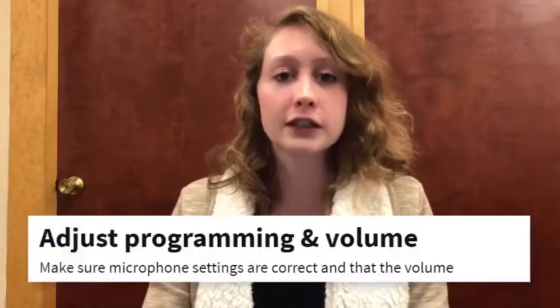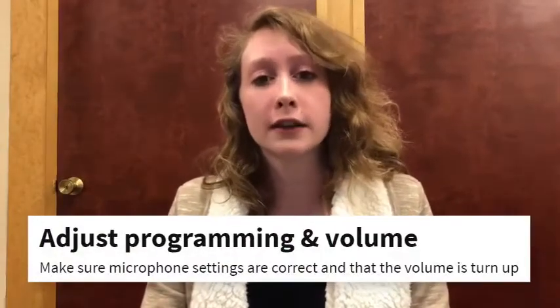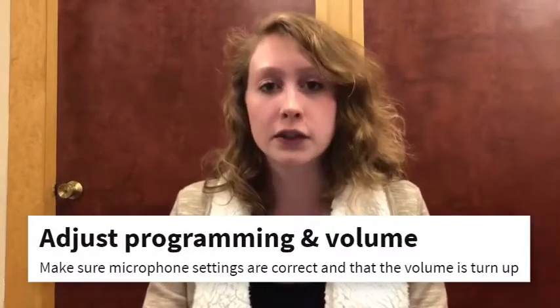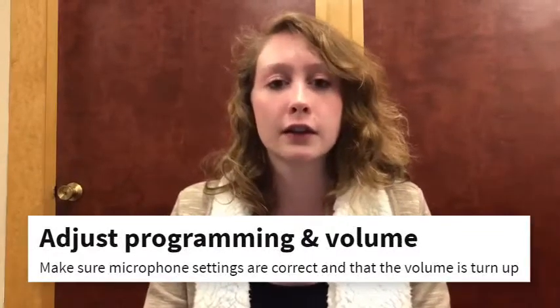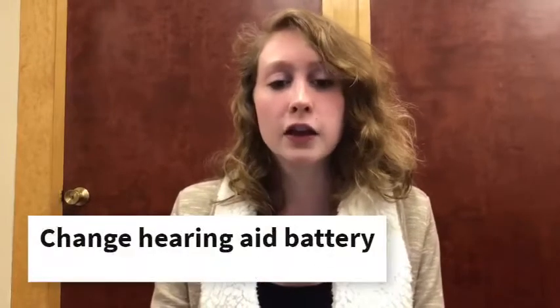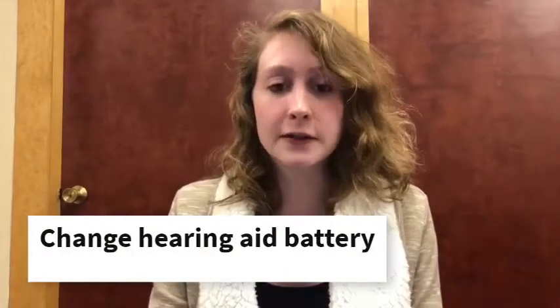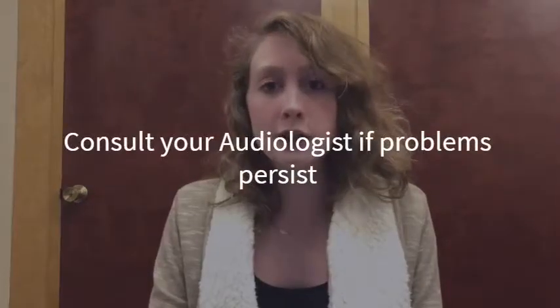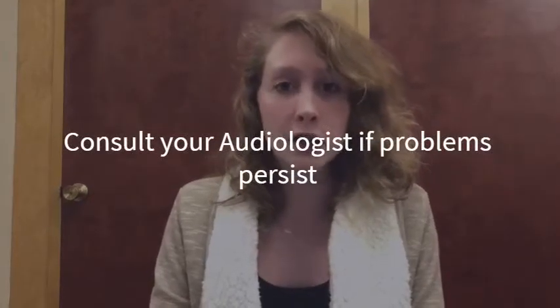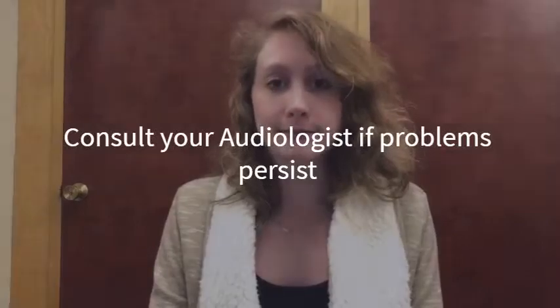The next thing that you should check, if you have already cleaned out your earpiece and made sure that it's inserted correctly into your ear canal, is to double check the settings to make sure that your volume is turned up loud enough and to also double check that you have the microphone settings on correctly. If you have already checked all of these settings and made sure that your hearing aid is programmed correctly, you should consider changing your hearing aid battery. If you've done this and you're still experiencing problems, consult your audiologist so that they can make sure that your hearing aid is not broken or damaged.